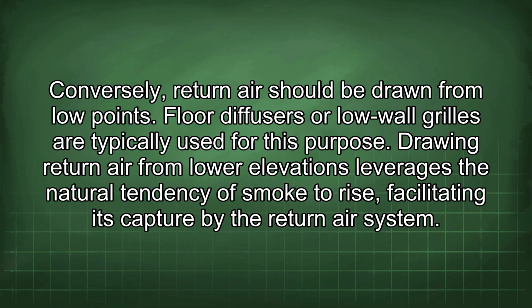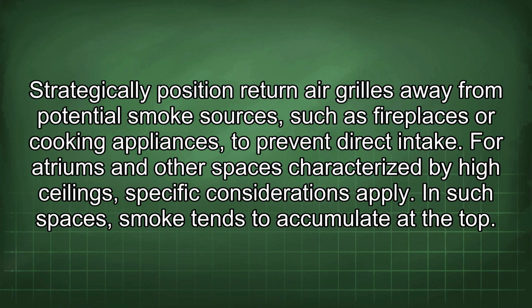Conversely, return air should be drawn from low points. Floor diffusers or low wall grills are typically used for this purpose. Drawing return air from lower elevations leverages the natural tendency of smoke to rise, facilitating its capture by the return air system. Strategically position return air grills away from potential smoke sources, such as fireplaces or cooking appliances, to prevent direct intake. For atriums and other spaces characterized by high ceilings, specific considerations apply.